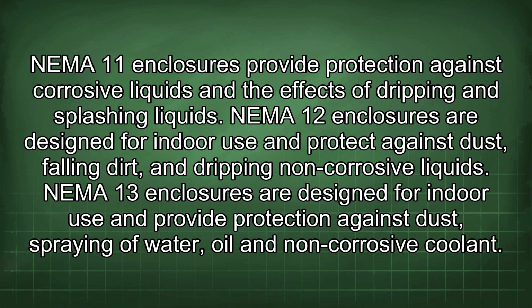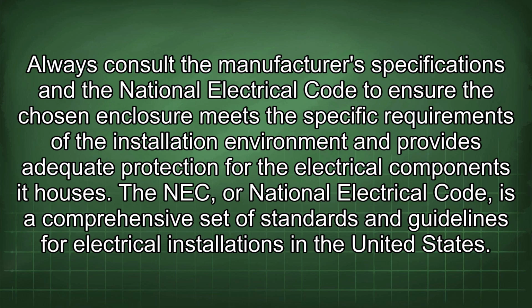NEMA 12 enclosures are designed for indoor use and protect against dust, falling dirt, and dripping non-corrosive liquids. NEMA 13 enclosures are designed for indoor use and provide protection against dust, spraying of water, oil, and non-corrosive coolant. Always consult the manufacturer's specifications and the National Electrical Code to ensure the chosen enclosure meets the specific requirements of the installation environment and provides adequate protection for the electrical components it houses.